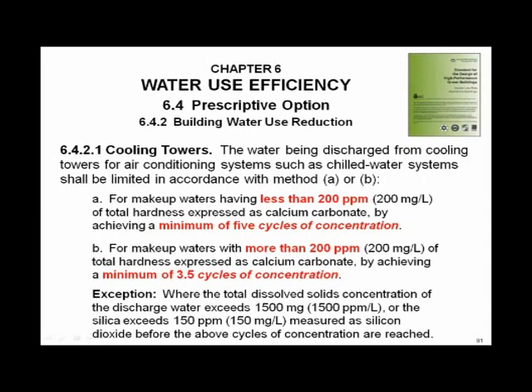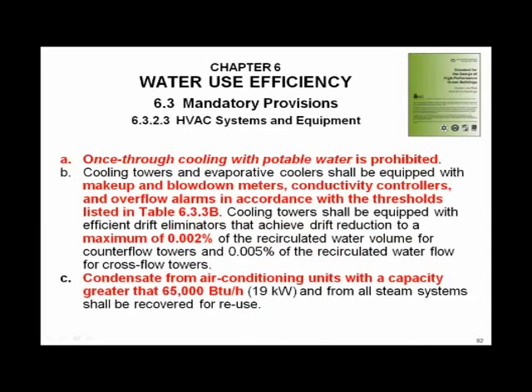Take a look. If you've got less than 200 parts per million of solids, or rocks, in your water, the minimum is 5 cycles of concentration. If you're out west and you've got hard water, over 200 parts per million, 3.5 cycles would be the concentration. The point is, you're going to be asked to control your blowdown rates based on cycles of concentration.